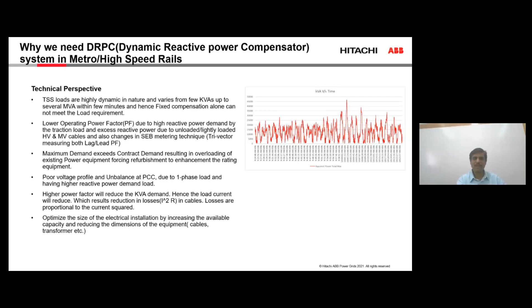Now, if you look at the commercial perspective of why we need a DRPC system, a direct connection is that whenever the power factor goes down, we are talking about penalty as a loss, and when we improve the power factor, we are also talking about incentive on the other side. So we have penalty for poor power factor, and we have incentive. Then the state electricity boards have been continuously increasing the target power factor, and right now they are talking about 0.98 as the target power factor. If you look at the incremental penalty, the poorer the power factor becomes, the more steeply the penalty will increase. And so it is with the incentives on the other side.